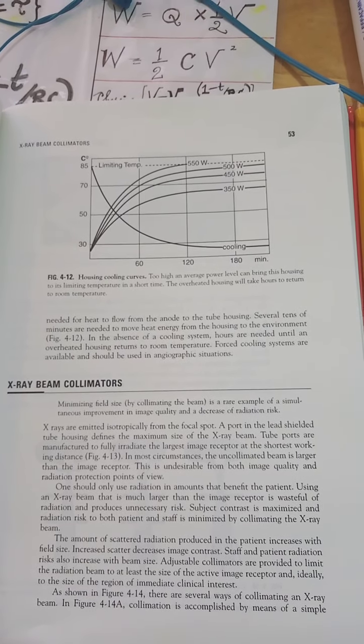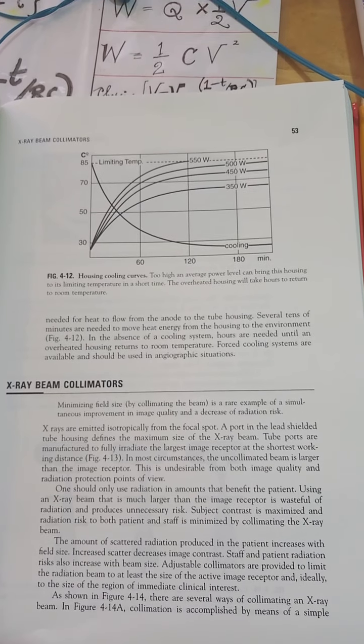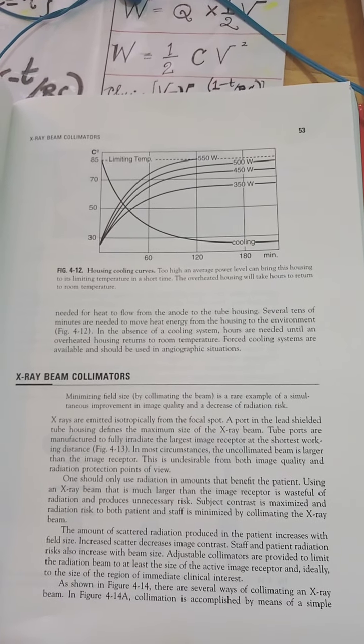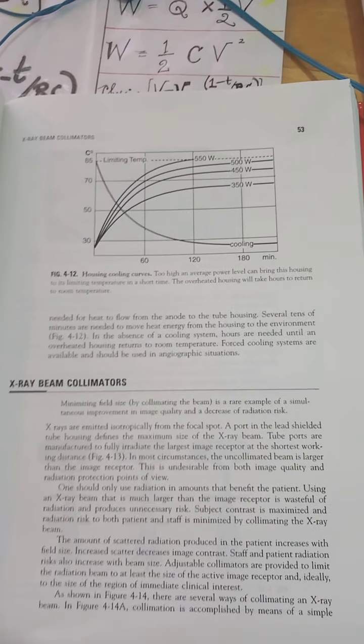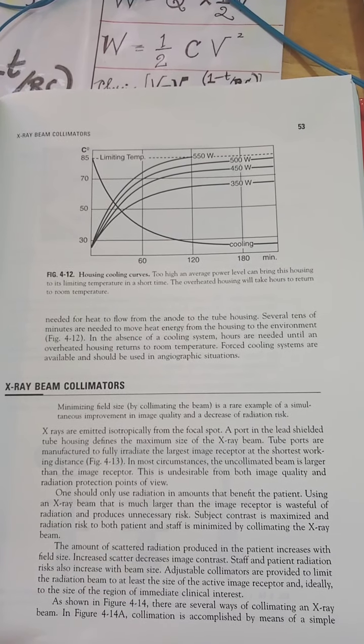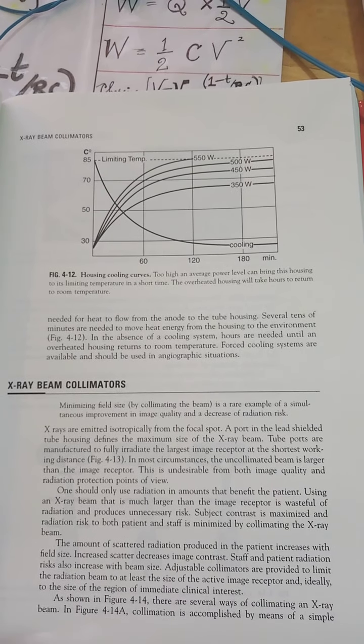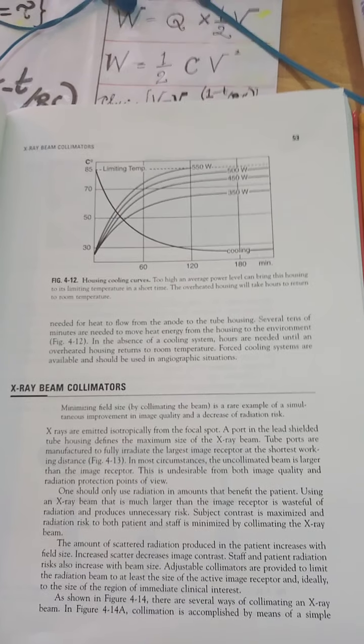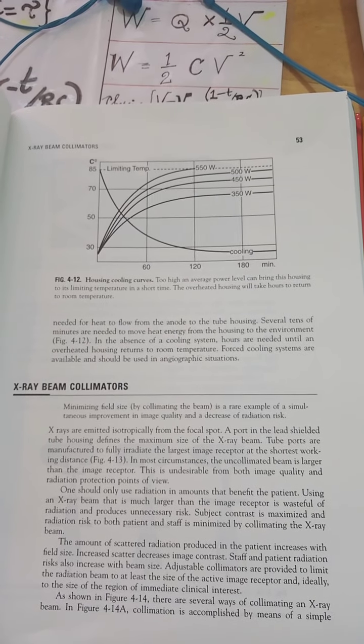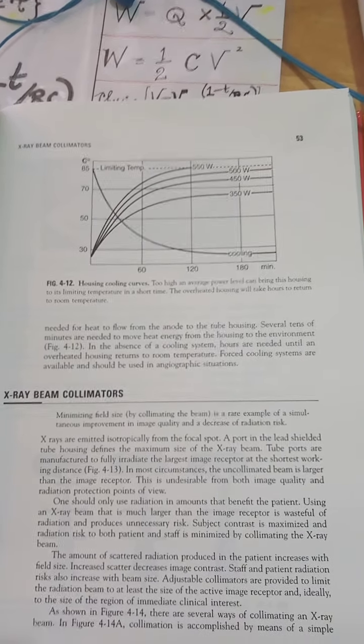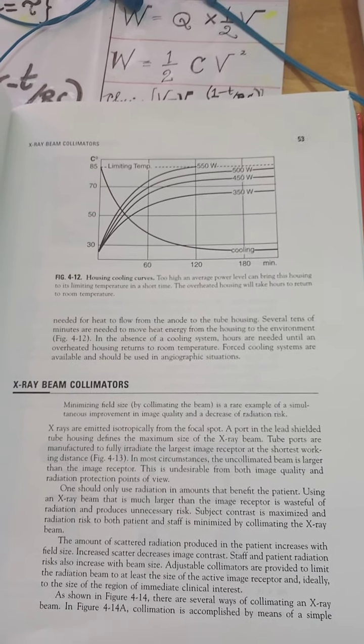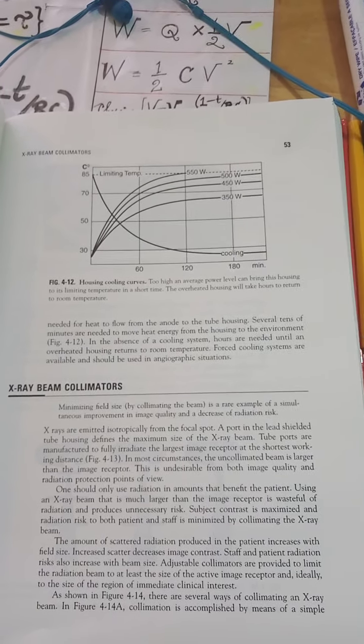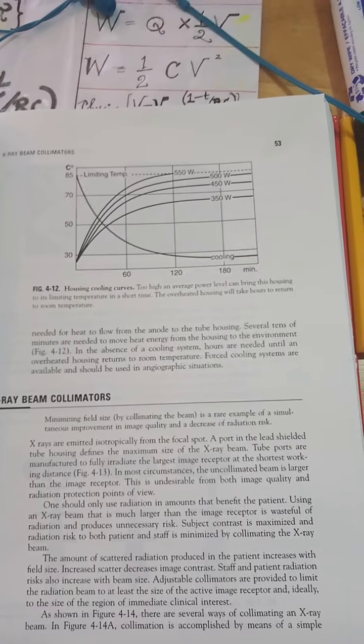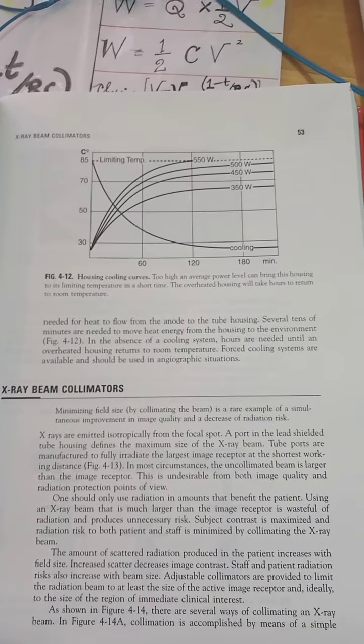X-rays are emitted isotropically, i.e. in all directions from the focal spot. A port in the lead-shielded tube housing defines the maximum size of the X-ray beam. Tube ports are manufactured to fully irradiate the largest image receptor at the shortest working distance. In most circumstances, the uncollimated beam is larger than the image receptor. This is undesirable from the point of view of image quality and radiation protection.